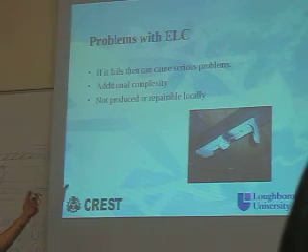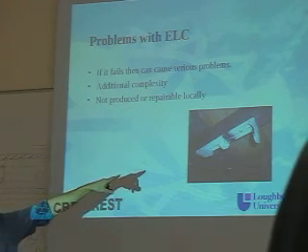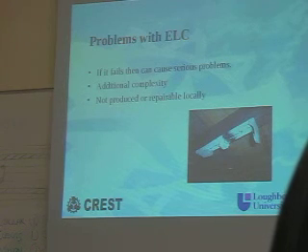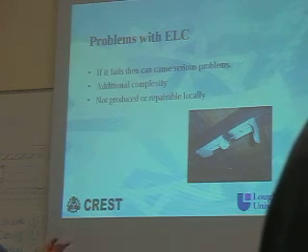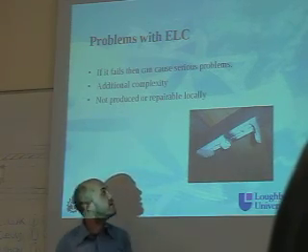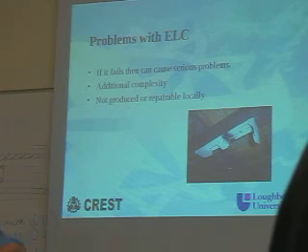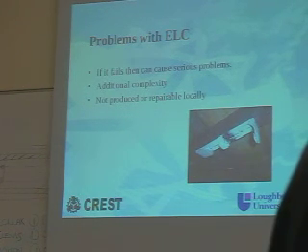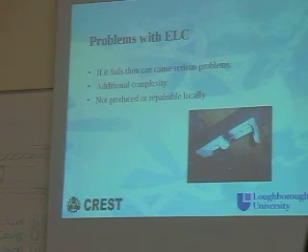If it fails, it can cause serious problems. In this particular situation, there was no fusing, no protection of any of the loads. So when it overvoltaged, it just overvoltaged, and this is a lighting ballast which has caught fire or got very hot, and every single light in the community had blown up at that point, which is a bit annoying, costs people quite a lot of money. So yeah, that's one of the problems. If it fails, you can get overvoltage, and that can cause serious problems. Also, they're not produced locally, generally not produced locally. There's not huge demand for it.